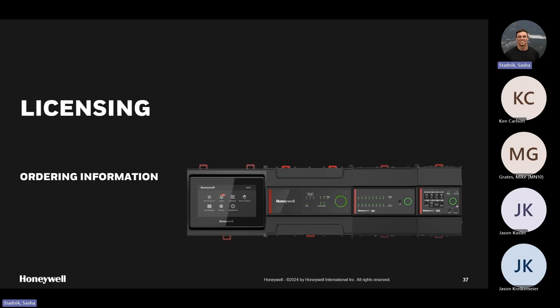On the licensing scheme, it works exactly like Tridium, except for the IO module, because there are panel buses. So every single license comes with a panel bus with X amount of points. Like this one, for example, has 100 panel bus points. That means I can attach to that controller, which has that license, 100 input and output points - not 100 IO modules, 100 input and output points.